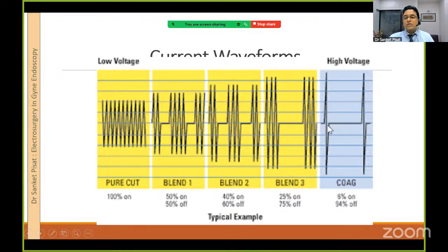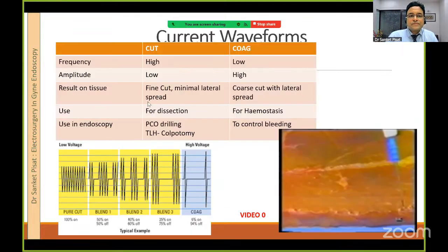This gap between the two waves, you can see 100% on on the left side versus 6% on and 94% off on the right side. It is this gap which provides for coagulation and does not allow cutting. So on the left, high frequency waves of lower amplitude or lower voltage cause the cutting effect, and on the right, higher voltage waves but with less frequency cause the coagulation effect. And this is the main difference between the two waveforms. So between cut and coag, how does it differ? In cut the frequency is high and in coag it is low.